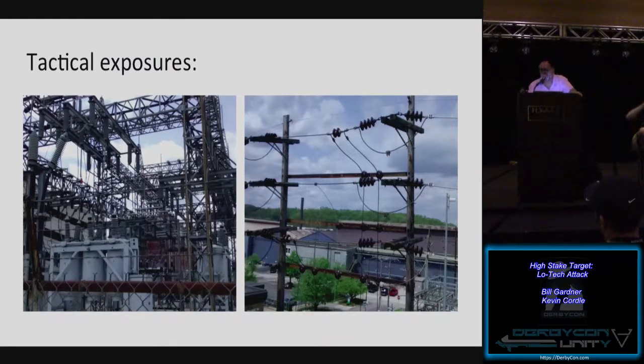Let me explain something about your power. Next time it starts storming and the power starts to go off, I'll tell you when it's really going to go off. Station breakers and reclosers operate three times on a different fault current curve.